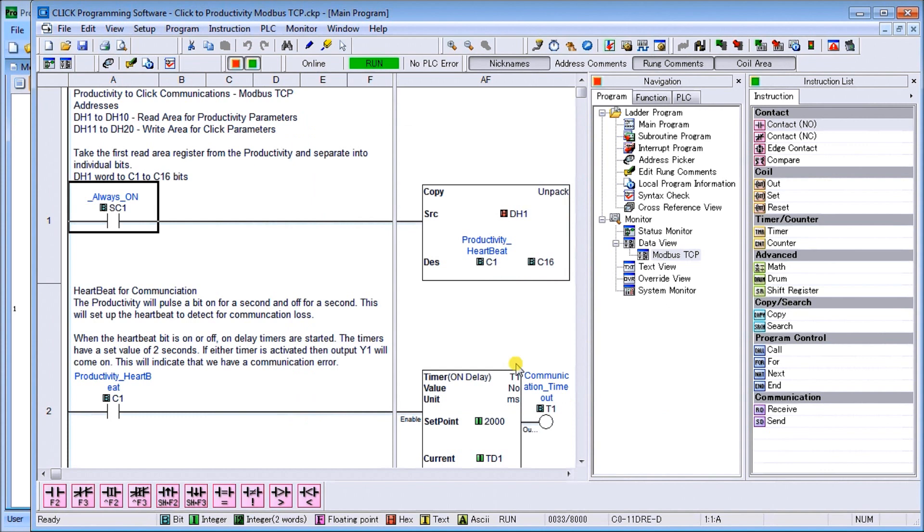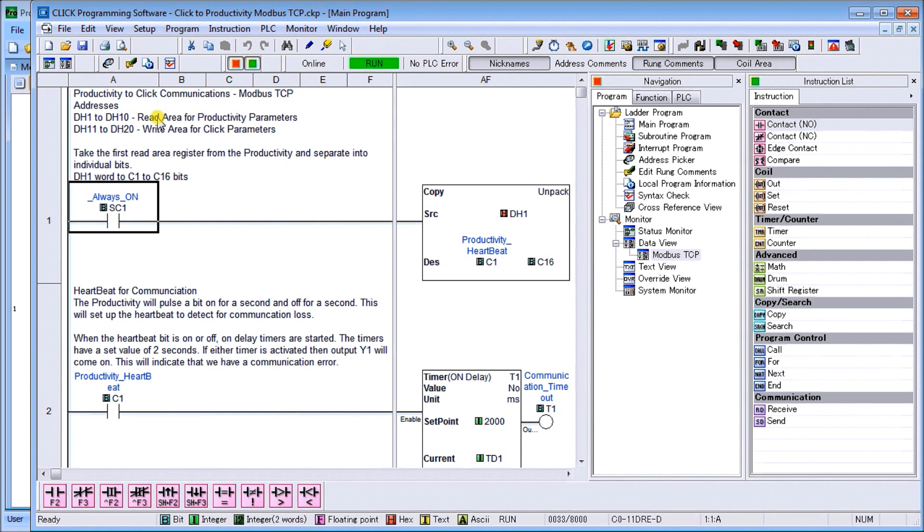That's our port setup. The next thing we need to do is determine the addresses that we're going to be using. In our particular case, DH1 to DH10 will be the read area from the Productivity, so the Productivity writing to those addresses from our point of view of the Click. DH11 to DH20 will be the write area for the Click, so that's what we're actually going to be writing to the Productivity series.